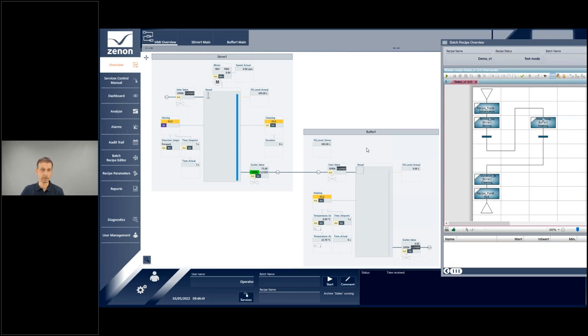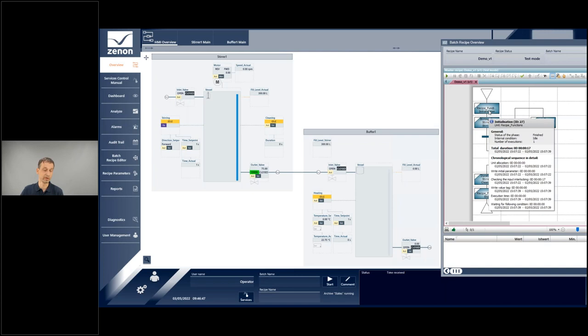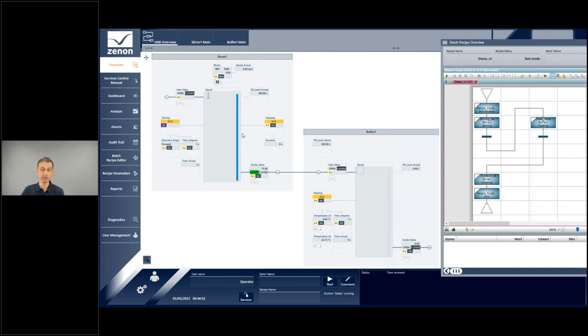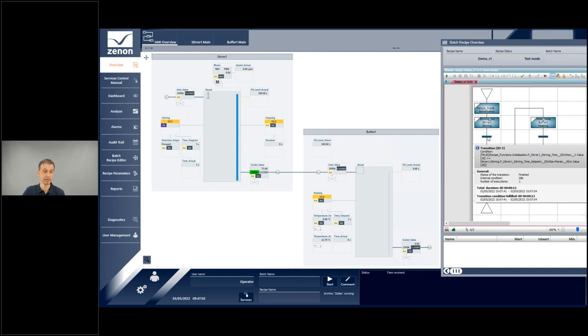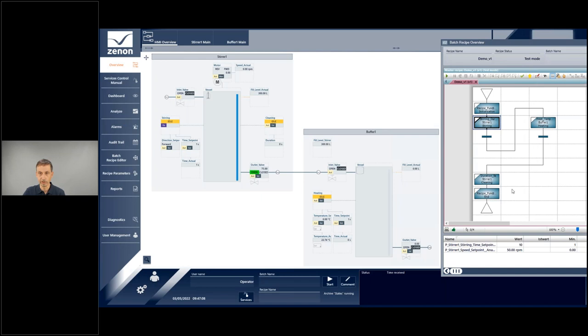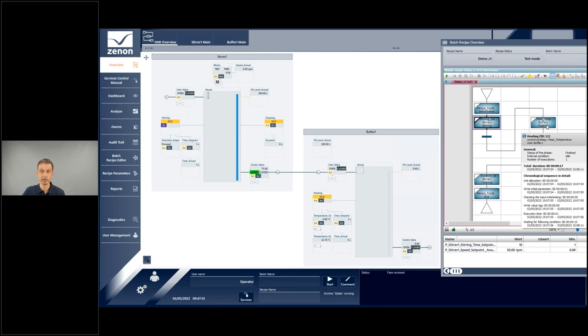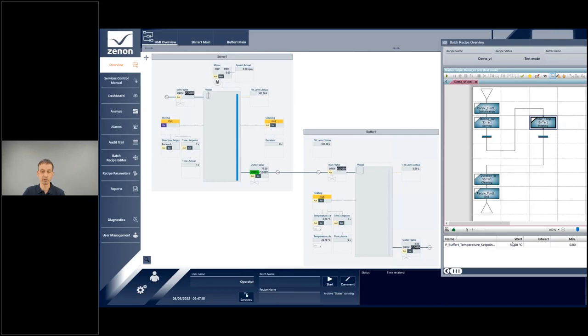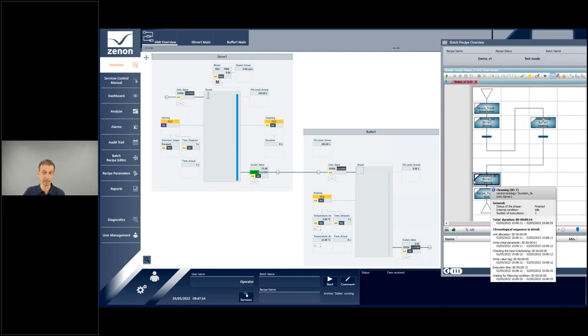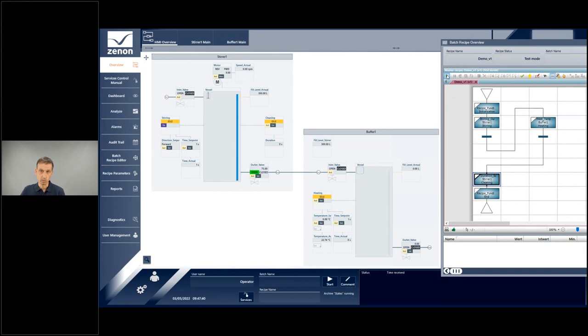In the batch editor, a master batch recipe is already available. On the left is some initialization of variables and starting archives. We have the stirring service of the stirrer — not a self-completing service procedure — with a transition saying when 10 seconds of duration is reached, the service is completed. For the heating service of the buffer, a setpoint temperature of 55°C is defined — when reached the service completes. Finally, the cleaning service of the stirrer is a self-completing procedure that automatically completes after 5 seconds.